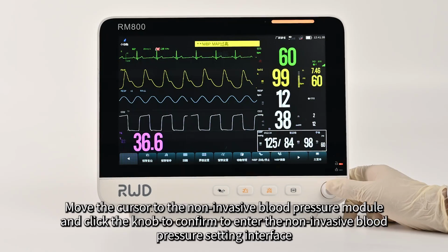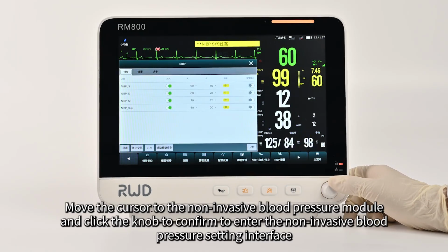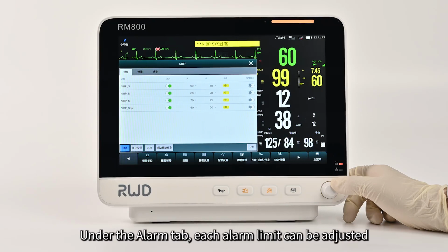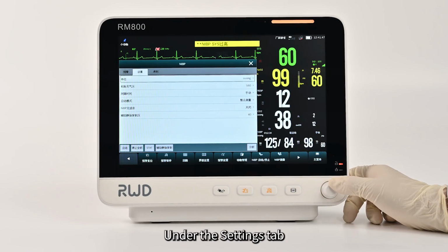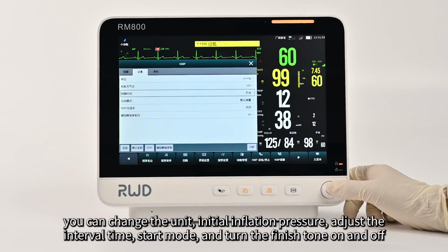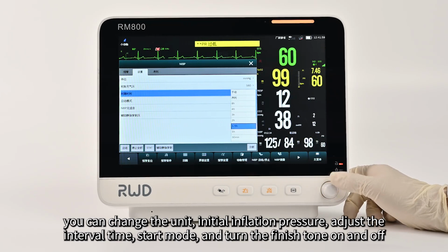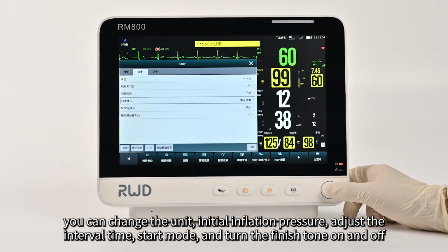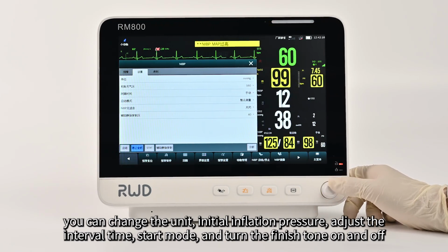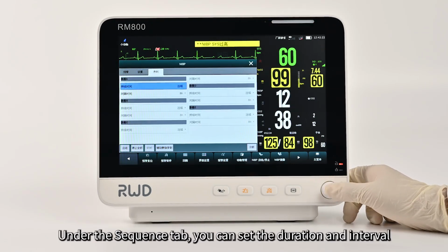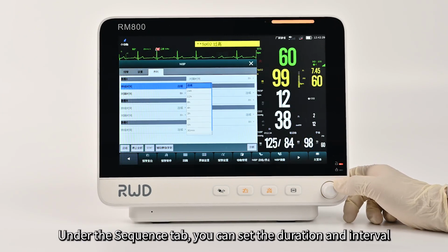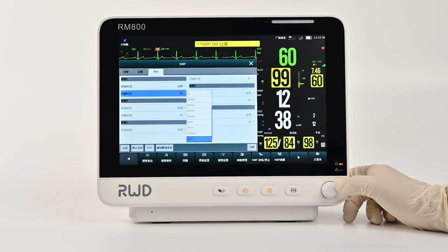Move the cursor to the non-invasive blood pressure module and click the knob to confirm to enter the non-invasive blood pressure setting interface. Under the Alarm tab, each alarm limit can be adjusted. Under the Settings tab, you can change the unit, initial inflation pressure, adjust the interval time, start mode, and turn the finish tone on and off. Under the Sequence tab, you can set the duration and interval.